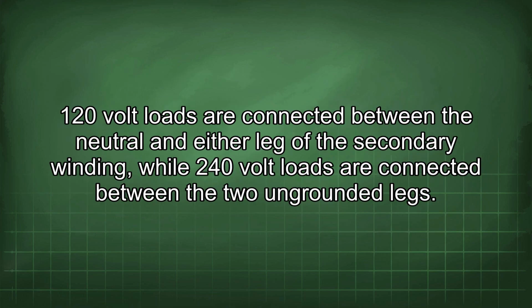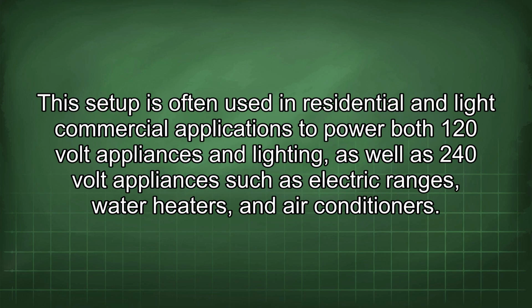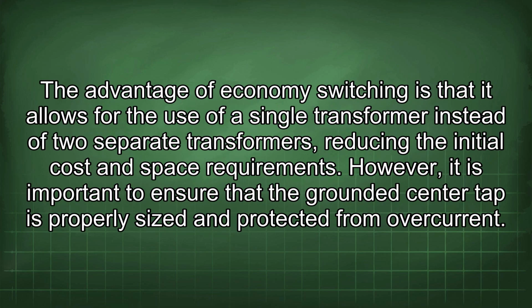120 volt loads are connected between the neutral and either leg of the secondary winding, while 240 volt loads are connected between the two ungrounded legs. This setup is often used in residential and light commercial applications to power both 120 volt appliances and lighting, as well as 240 volt appliances such as electric ranges, water heaters, and air conditioners. The advantage of economy switching is that it allows for the use of a single transformer instead of two separate transformers, reducing the initial cost and space requirements.